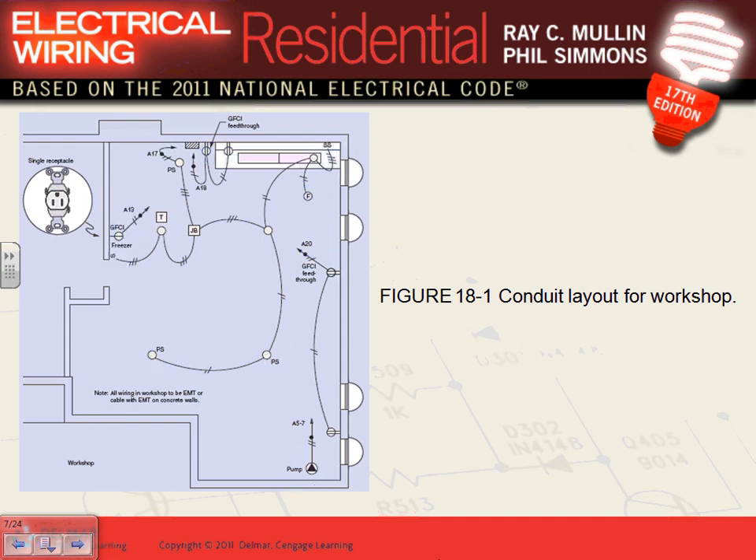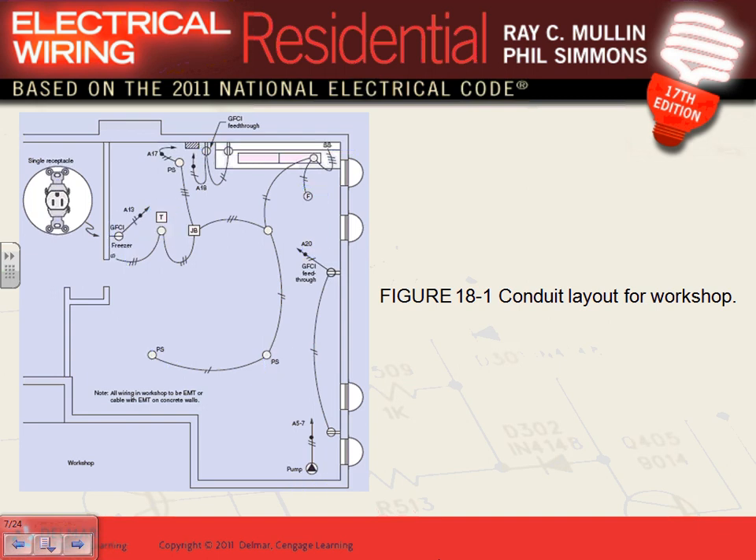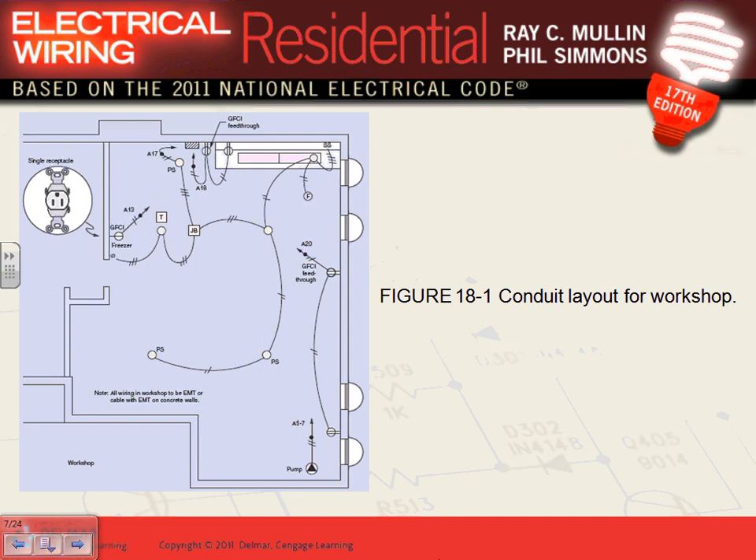There's a transformer here — that 'T' stands for transformer. This one is for the doorbell. You need to feed your doorbell from 120V, convert it to 24V, and go to your doorbell front and back and chime. In residential, they take a junction box in the basement, attach the transformer to it — nipple the transformer to the metallic box — and feed it directly from there.